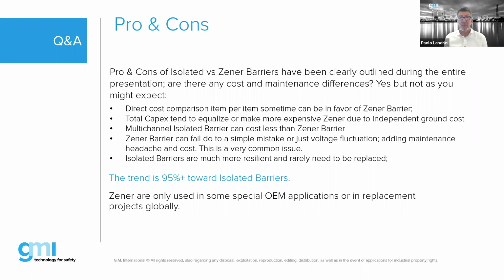Where do you see application for Zener barriers? Some special sensors, OEM sensors, some special application where an isolated barrier was never designed for, and it's a very limited application, so the cost to design it isn't worth it. Or when you have a project with many Zener barriers already installed—they keep blowing and you have to keep replacing them, so there's potential there, but this is typically for replacing existing installations. For new projects, in my experience over the last 10 years, I have not seen a new project requesting a Zener barrier.